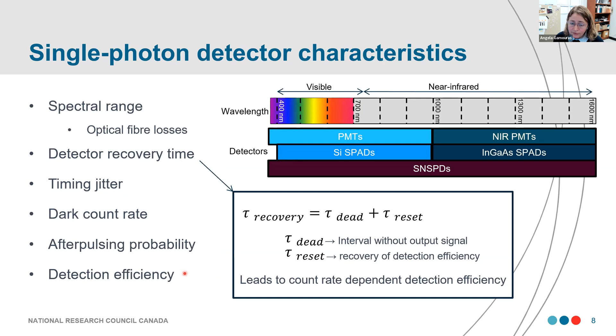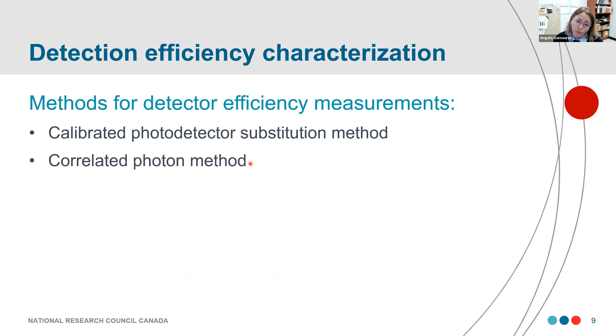There are two popular methods for doing that: the calibrated photodetector substitution method of calibration, and the correlated photon method of single photon detector calibration. At NRC, here's an apparatus we have in the lab to characterize single photon detectors using a substitution technique. Here we have an 850 nanometer laser diode. We have two neutral density filters, a photodetector that's been calibrated traceable to the SI system of units, and our detector under test, the single photon detector.